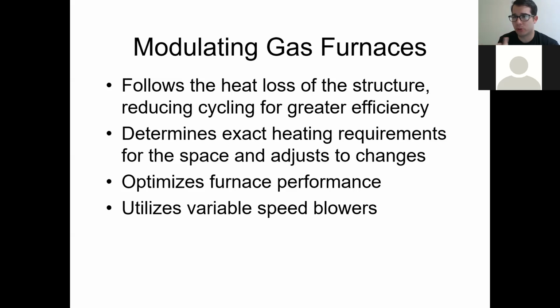The variable speed motors are one of the biggest things, but the variable speed gas valve is the biggest thing. That's one of the hardest things to troubleshoot, that gas valve.